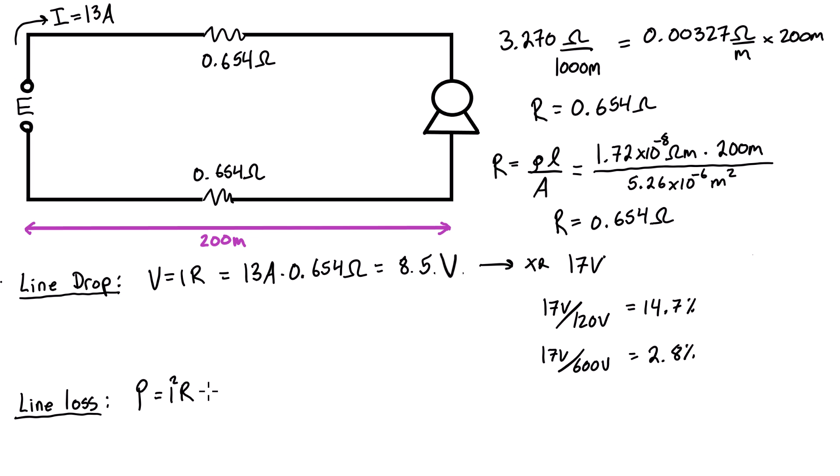We can just plug in the values that we have. We have the current, it is 13 amps, we're going to square that, and we're going to multiply it by the resistance. I'll just do one line each—you could do the whole circuit at once if you want. So we have 0.654 ohms, and we're going to get a value of 110.5 watts in each line, or we can multiply that by two for the entire circuit and we're going to get 221 watts for the entire circuit. So that answers the question: the line drop is 17 volts for the whole circuit and the line loss is 221 watts for the whole circuit.